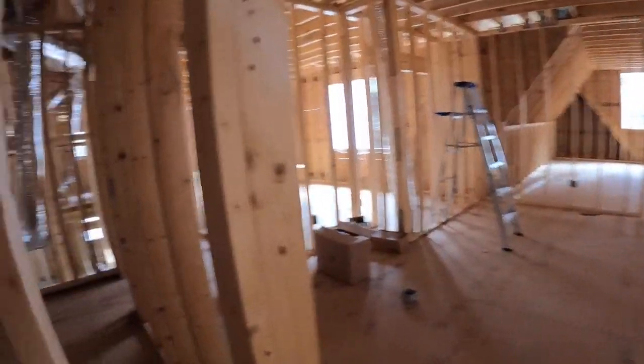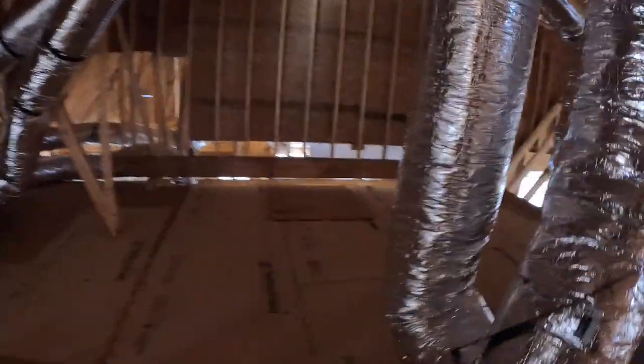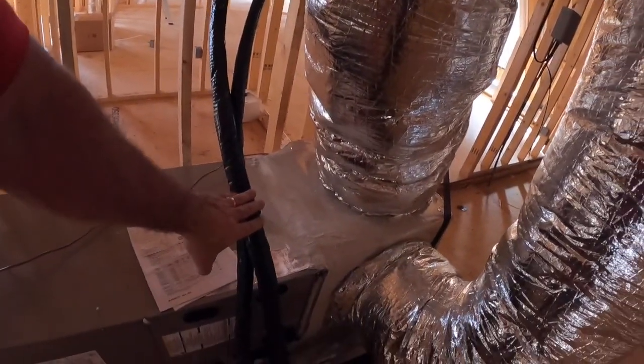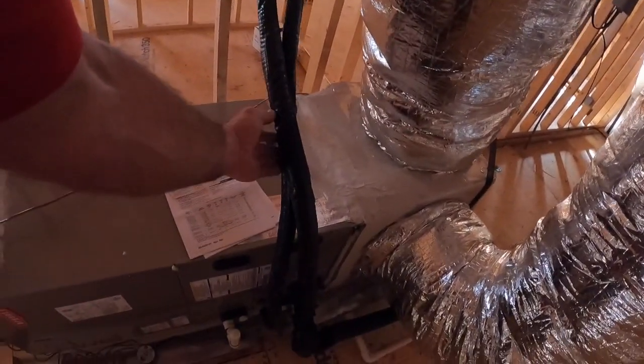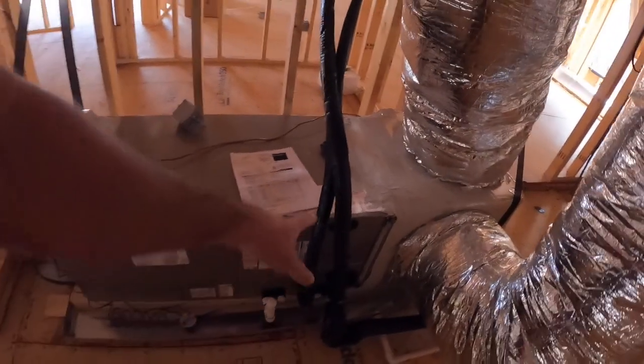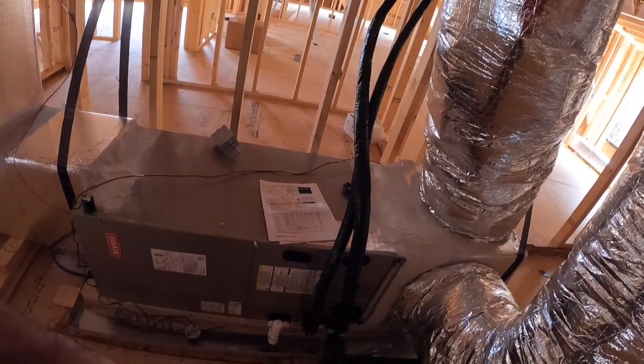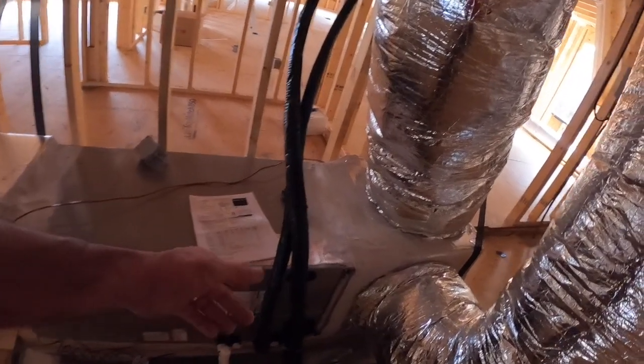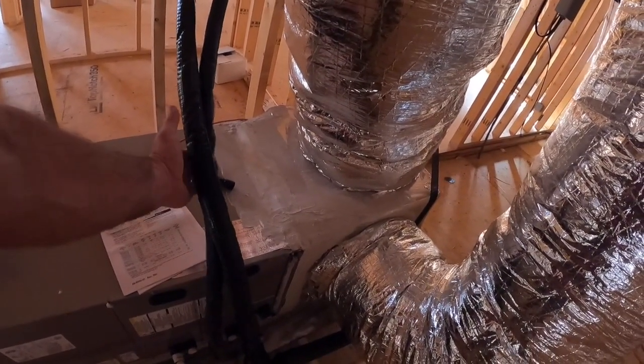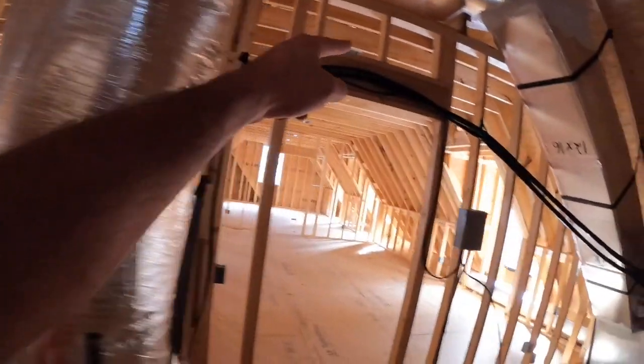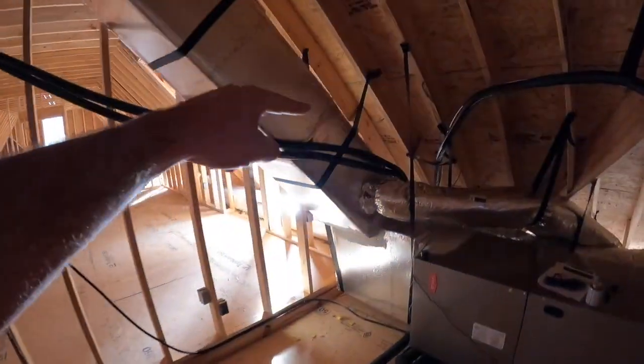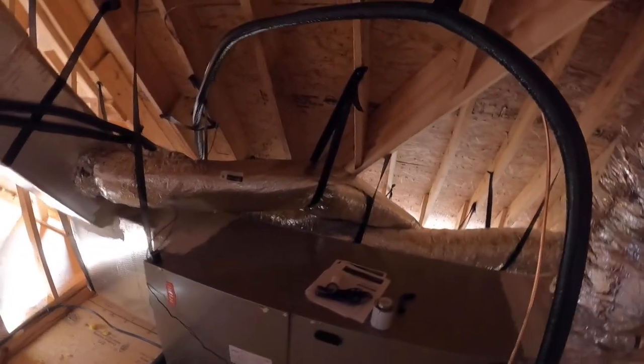Right, so also didn't cover the copper line. The refrigerant has to flow from the outside unit to the inside unit. The liquid line here doesn't have to be insulated, but the mini split lines were all they had at the time I ordered this. That's why this one's insulated. But that copper runs up and over and downstairs. Same thing with this one, up and over, downstairs.